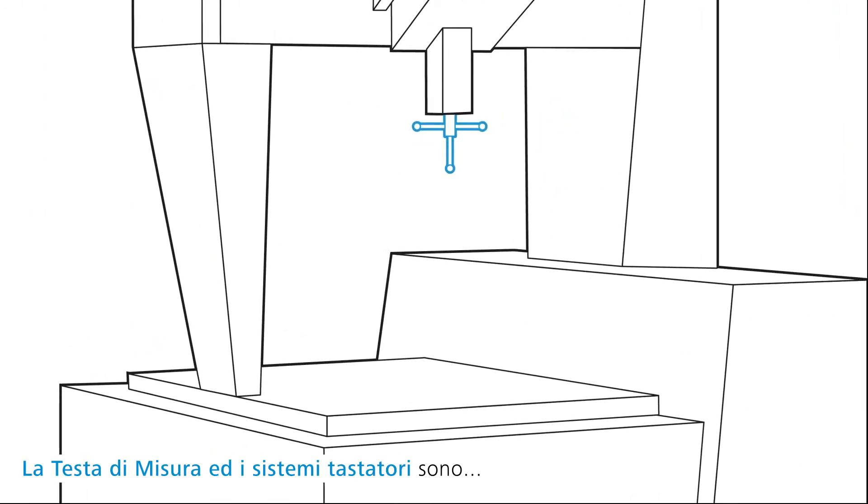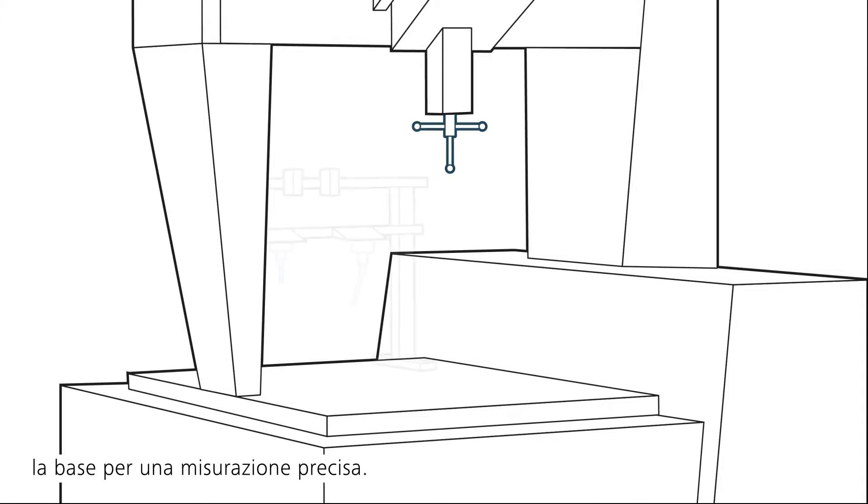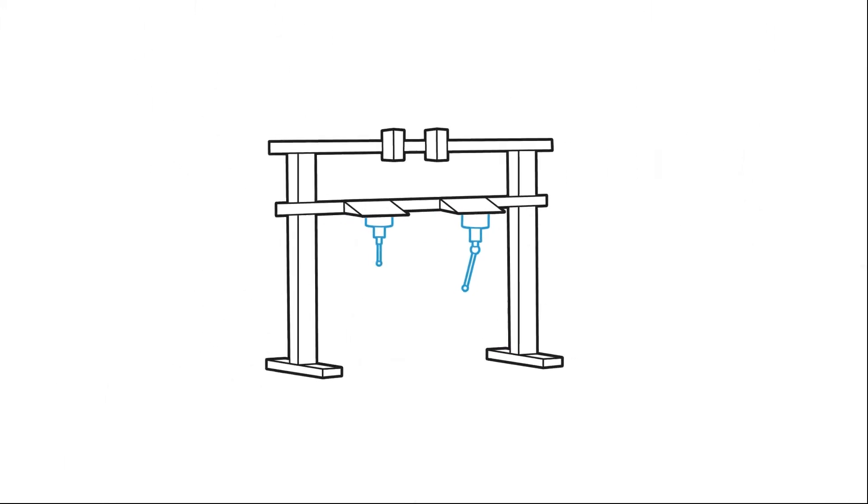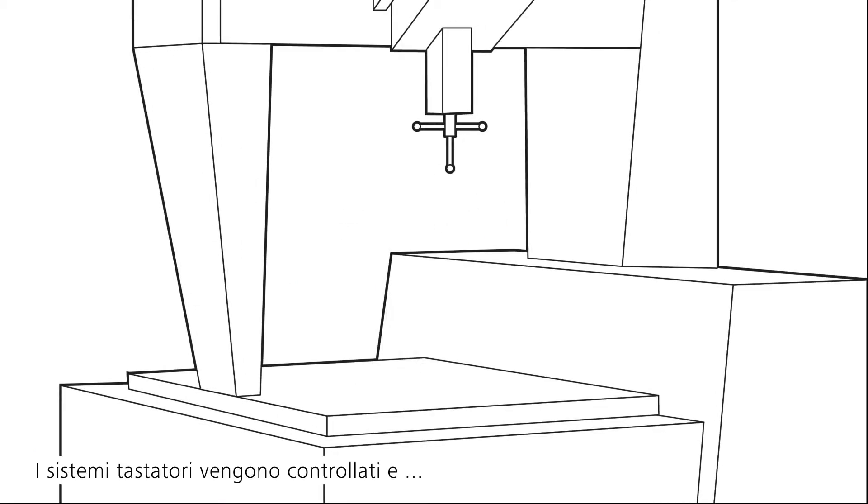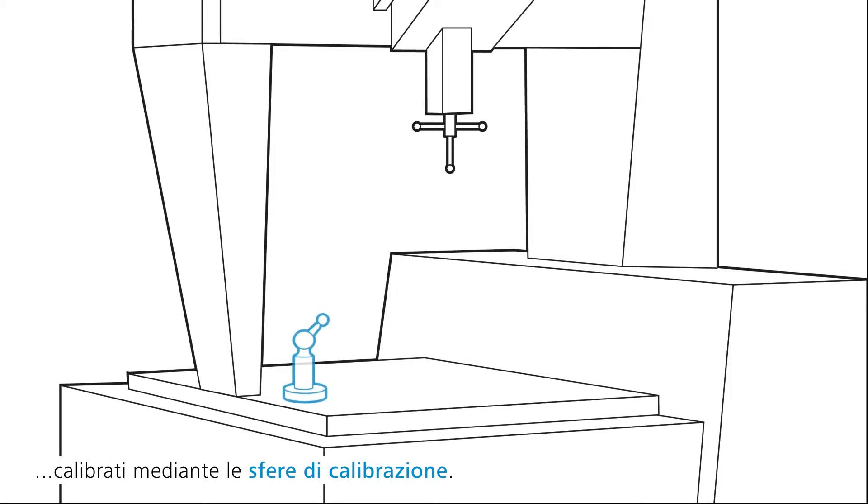Sensors and stylus systems are the basis for precise measuring results. They are stored on the multi-sensor rack and provided for automatic change by the CMM. The stylus systems are calibrated by means of reference spheres.